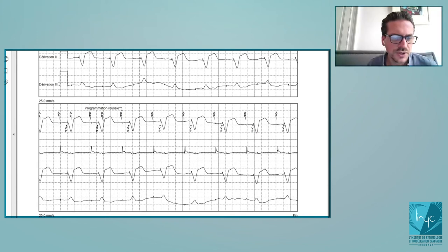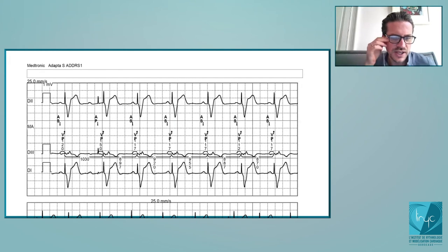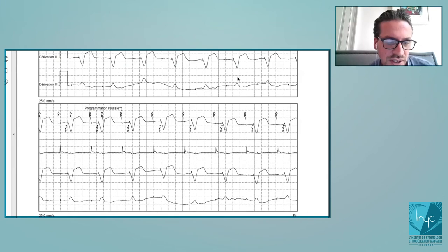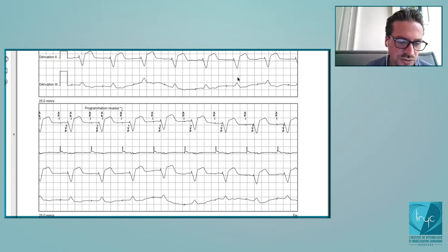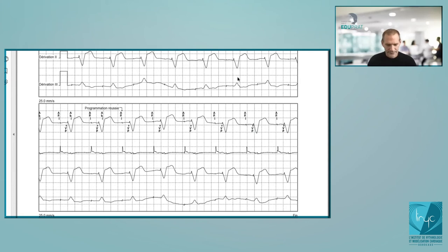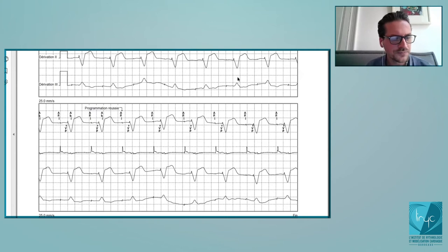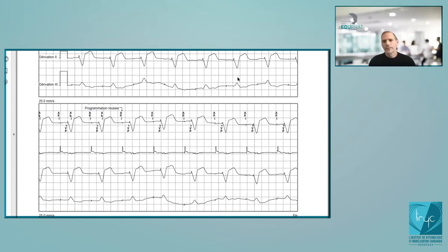Question: we see those AB markers and you say they have an influence on the atrial fibrillation counter — do they also influence the rates during which the pacemaker is working? No. A signal that falls inside the blanking or in the refractory will not modify the rate. A signal labeled AB will not inhibit atrial pacing.